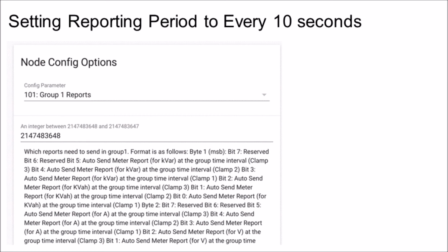For example, a Z-Wave network can support over 250 Z-Wave devices at once, but a single energy monitor reporting its data every 10 seconds can take up 20% of the Z-Wave bandwidth capacity, at which point the network does not function well if it's exceeded. But for our needs, we need that granular 10-second energy data because we use it for our energy monitor and we use it for our load controls. And so, we need that granular data.